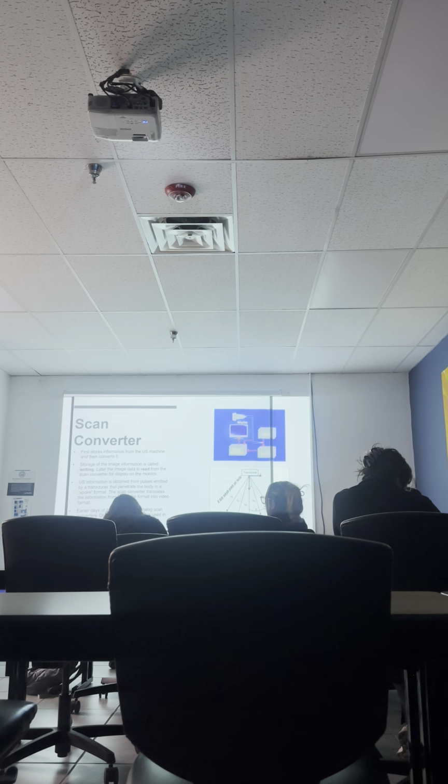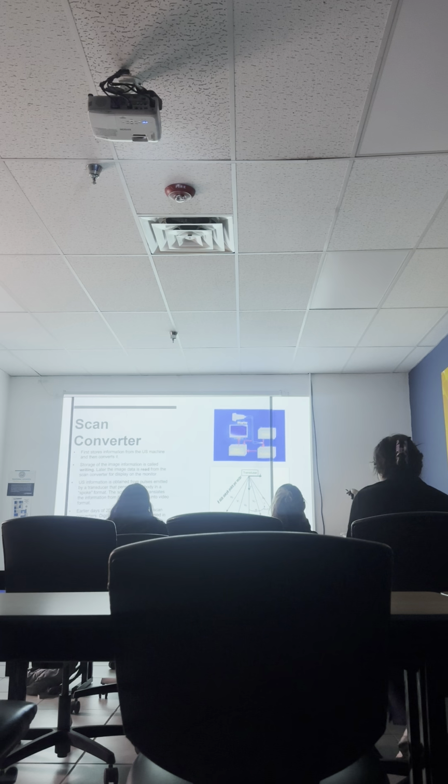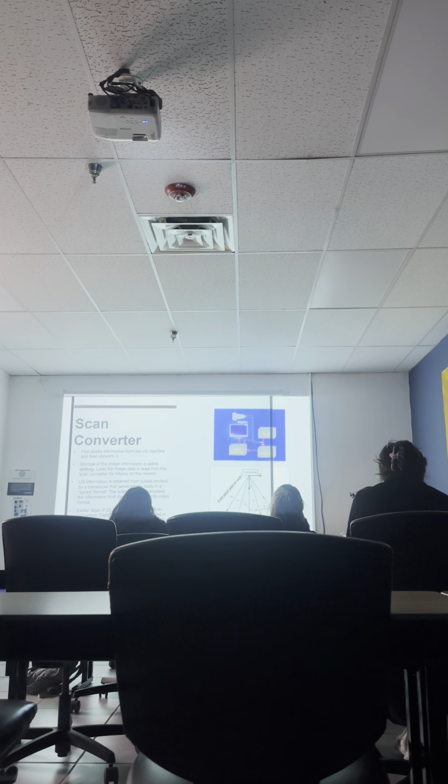Yes. On the picture, it shows how it works right from the transducer to the pulser receiver. But it also has a pulser straight to the scan converter. Could you explain that? So when we're sending out the pulse, it's not the pulser straight to the scan converter, it's the information from the pulser.